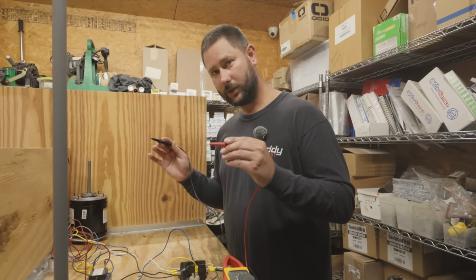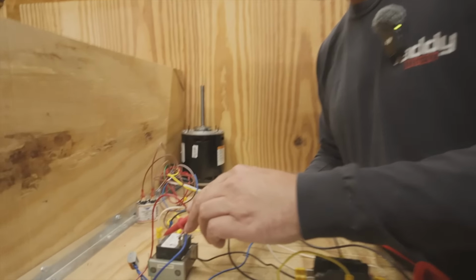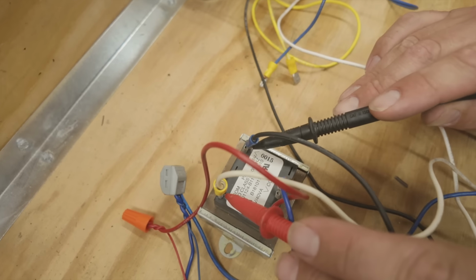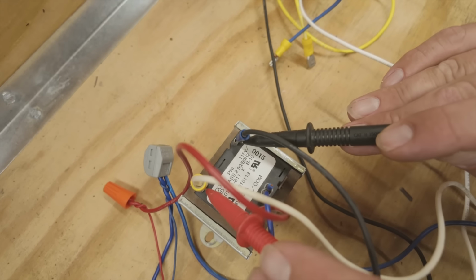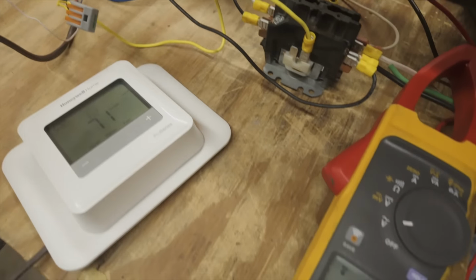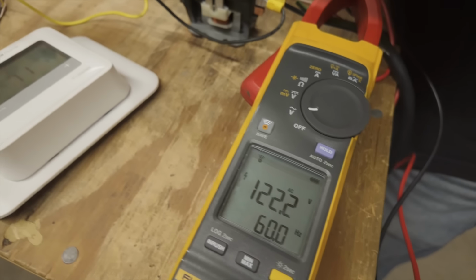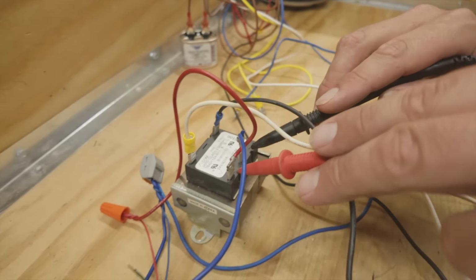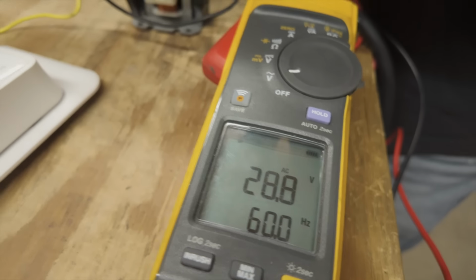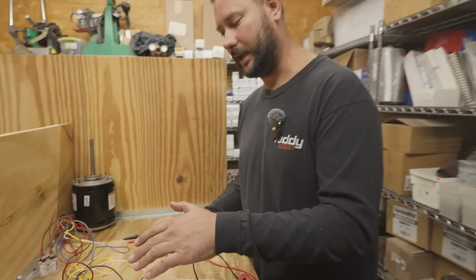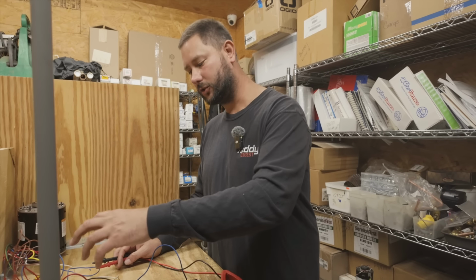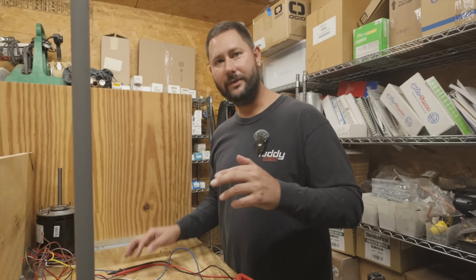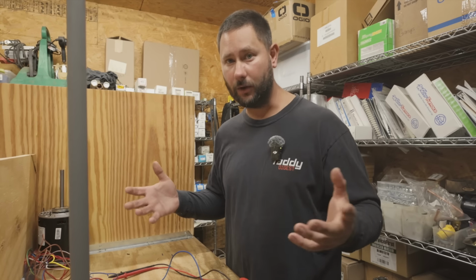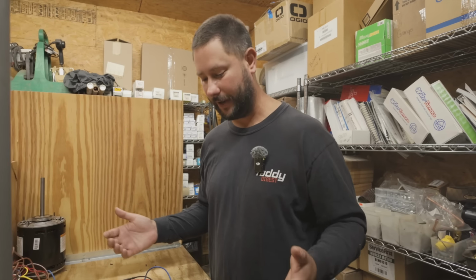120 volts, see that? Now, just so you know, right here on your transformer, because we need to learn how to check it, our primary side right here, common to 115, has got 120. Okay, check out the meter, 120. And then if you check the secondary side right here, common to 24, we've got our 28 volts. So we're providing the thermostat with control voltage via the transformer, okay? Without the transformer, the thermostat would have no display, unless we had batteries to power it.